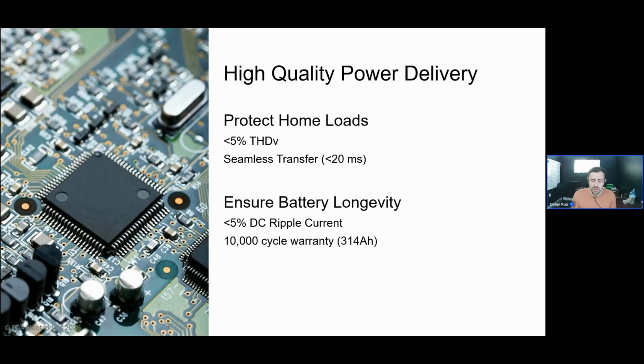Now, on the DC side, probably even more impressive when you compare us to our competitors in the industry, we really have taken steps to ensure that this unit is designed to deliver and ensure battery longevity. DC ripple current is not something that I hear talked about a lot, but is an important design consideration with these systems. Essentially, DC ripple current are ripples in the DC energy flow to the batteries of the system that can be caused by high frequency oscillations that are introduced by the power electronics necessary to output AC power with the system. So essentially, it makes the DC power to the batteries behave kind of like AC with a lot of oscillations within that power output.